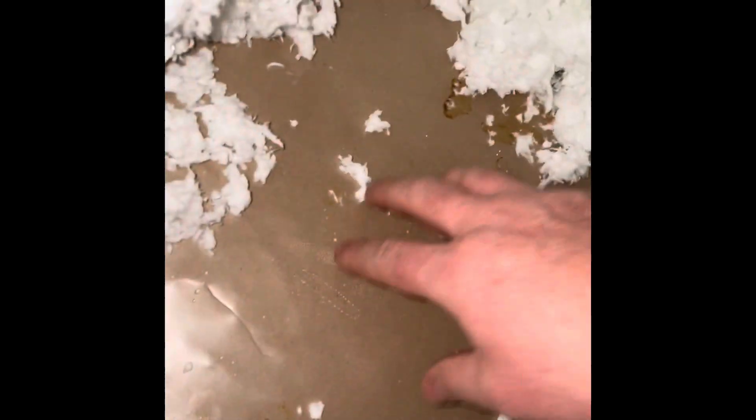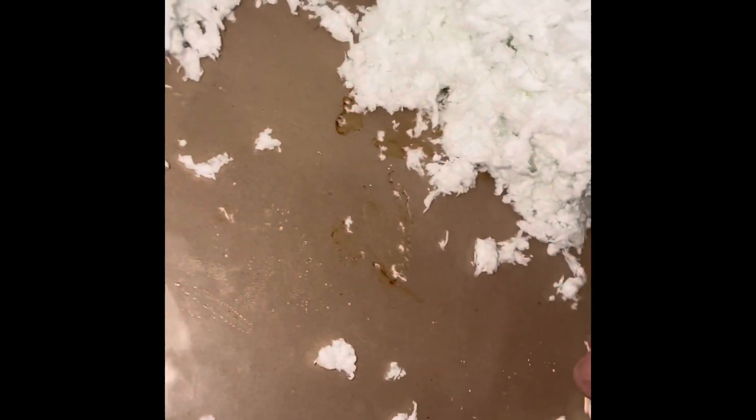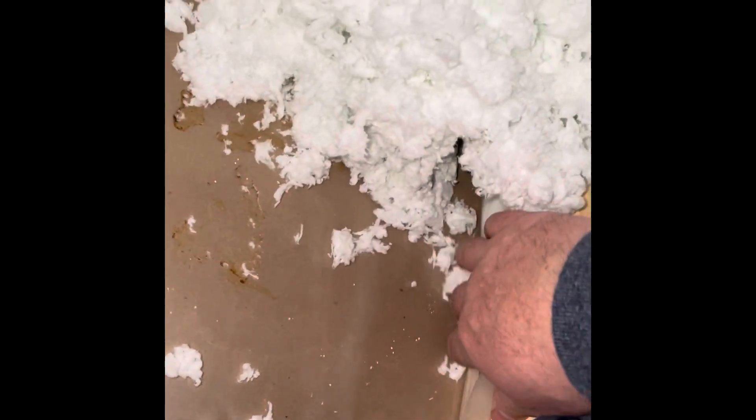And if that happens, you'll start to see pooling on the sheeting. The important thing is if the vapor barrier is doing its job, it'll catch on this side of the attic, evaporate eventually, and go away. But if you have a vapor barrier that's not sealed and it's just loose like this, moisture — if there's enough of it — can pool. You can see these water drips right there. It'll pool on the surface and then track along the plastic and get underneath these seams.